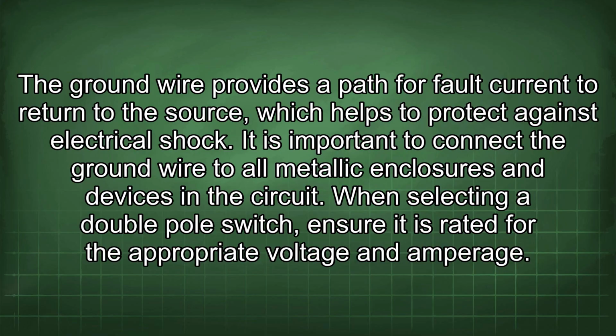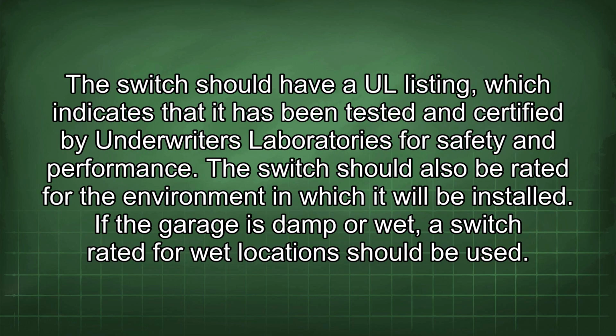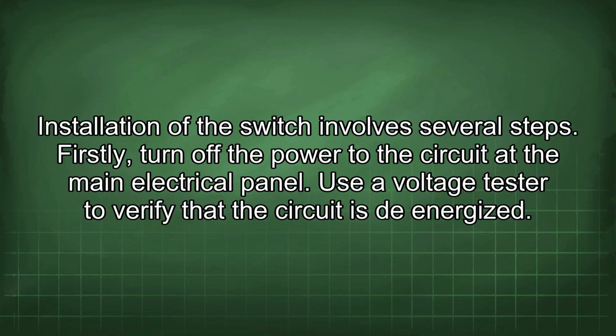It is important to connect the ground wire to all metallic enclosures and devices in the circuit. When selecting a double-pole switch, ensure it is rated for the appropriate voltage and amperage. The switch should have a UL listing, which indicates that it has been tested and certified by Underwriters Laboratories for safety and performance. The switch should also be rated for the environment in which it will be installed. If the garage is damp or wet, a switch rated for wet location should be used. Installation of the switch involves several steps. Firstly, turn off the power to the circuit at the main electrical panel.